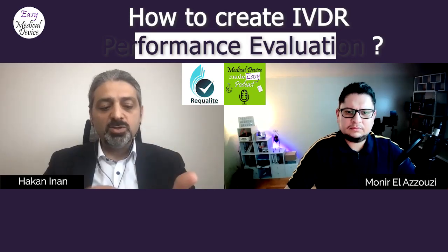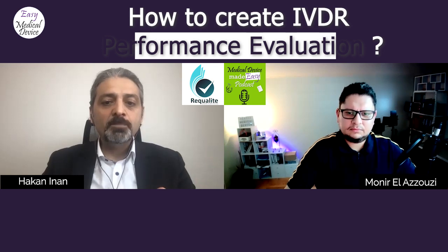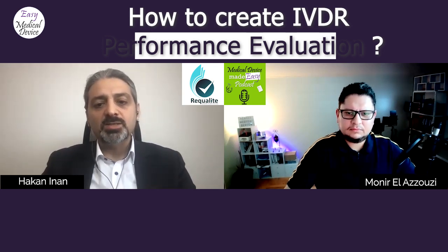Yeah. And secondly, as you know, there is the Global Harmonization Task Force, GHTF, which is now IMDRF, the International Medical Device Regulators Forum. And there are 3 documents from IMDRF under working group 5. So there are documents number 6, 7, and 8, which describe the parameters that we need to follow for performance evaluation, scientific validity, and clinical evidence for in vitro diagnostic devices.